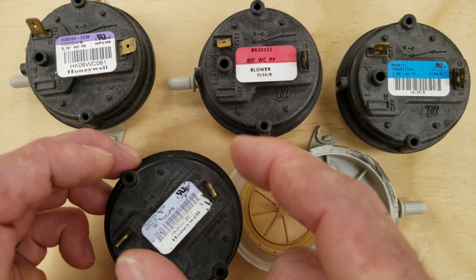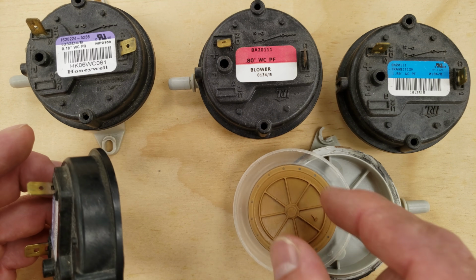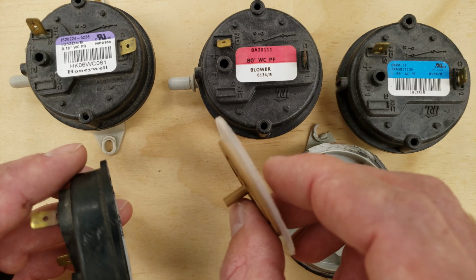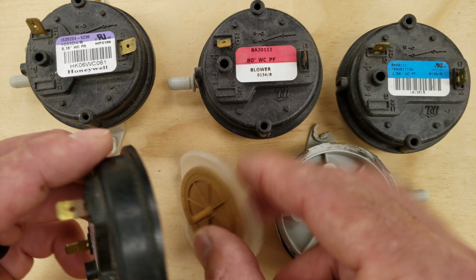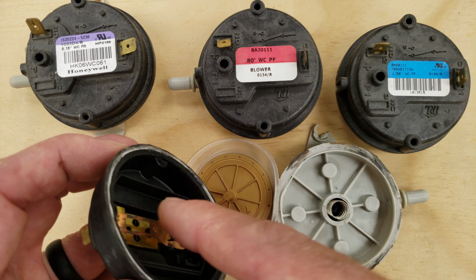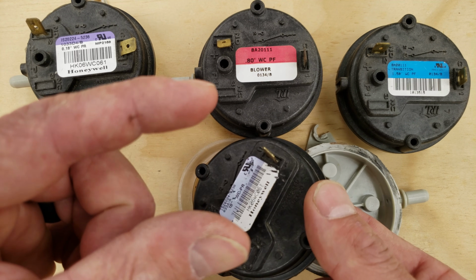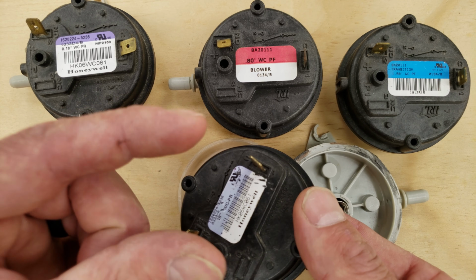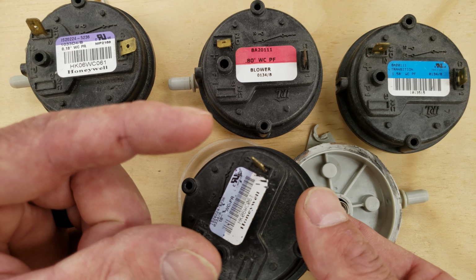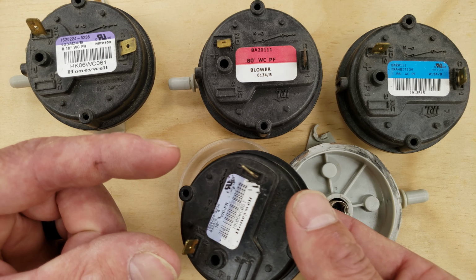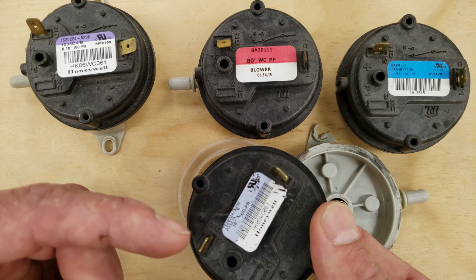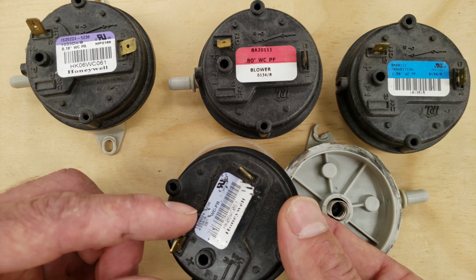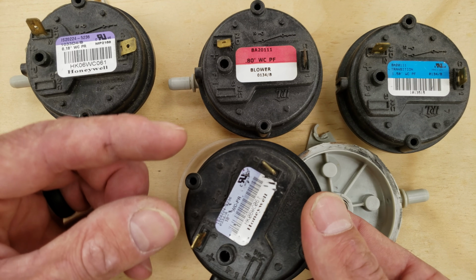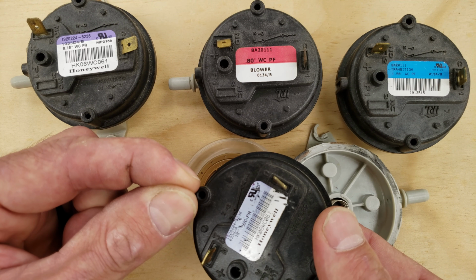So right now, this switch actually is closed. But the pressure switch usually has this little nub right here. It's pressing up on this, like this, and it's making this pressure switch be in the normally open position. So it's only going to close anytime that you have a pressure reduction greater than, in this case, 0.18 inch water column. And then the pressure switch is going to electrically close.